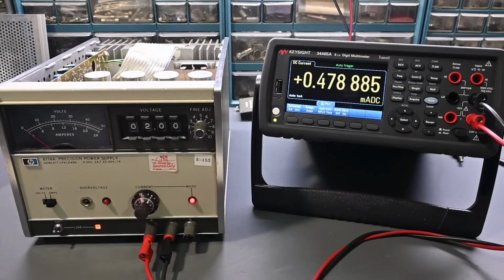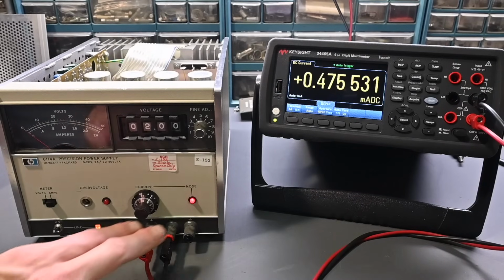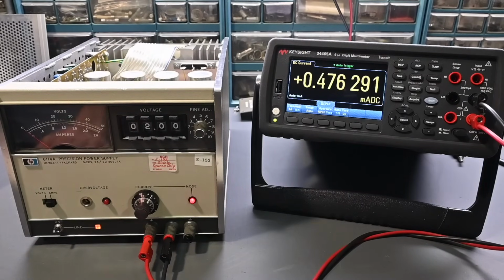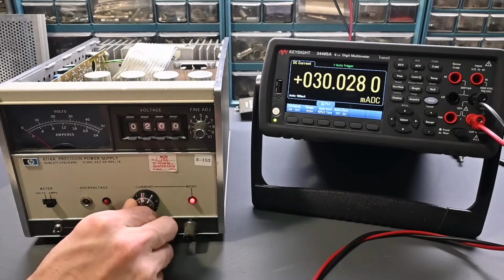Alright, so at this point the calibration is complete. Everything's dialed in and looking very good. So the final step is the amp meter calibration. It turned out very accurate as well. So you can see the digital multimeter is in the current measuring mode. It's just connected across the output terminals.